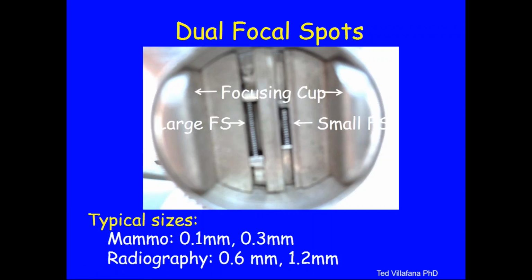Are smaller, and they are in sort of an indentation, like a little valley. You have these protrusions on either side. Those are the focusing cups. Remember we mentioned that the electrons coming off of these coils, these little helical filaments, go off in every which way direction, and you want to focus them to a small focal spot at the target. How do you do that?